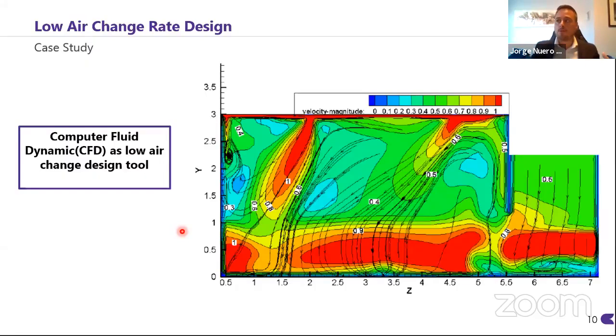I mean, in some rooms, if you go to the ISPE or to other recommended guidelines, you will see that, for example, for an ISO 8, 28 air changes per hour are recommended. But this is not always the case. In some facilities, you need a low air rate and a higher rate. So by defining, room by room, the velocities and the airflow inside that room, we can optimize the design a lot.